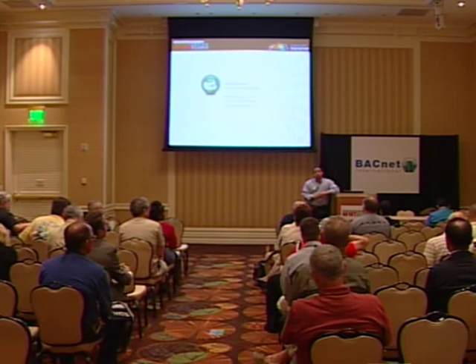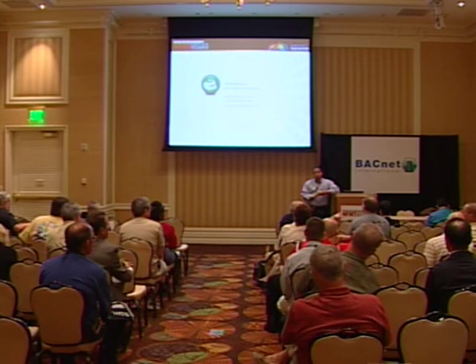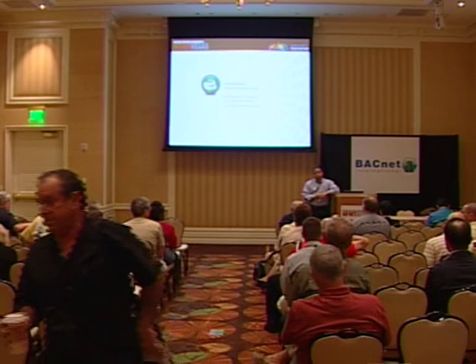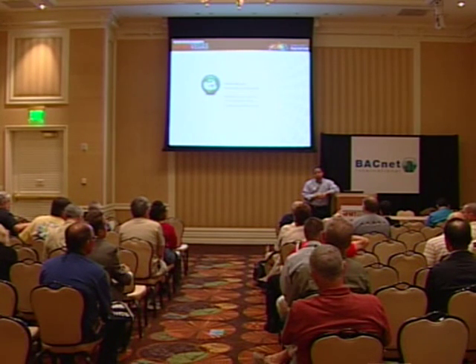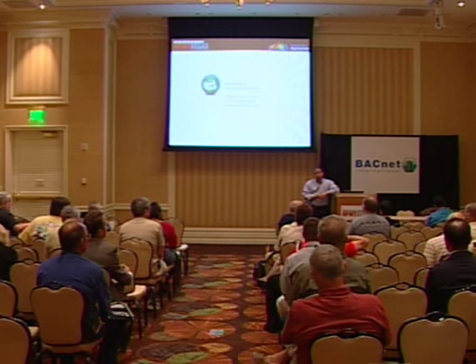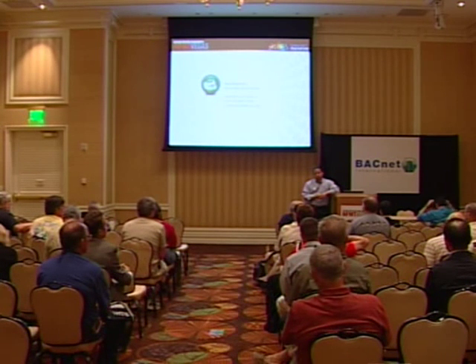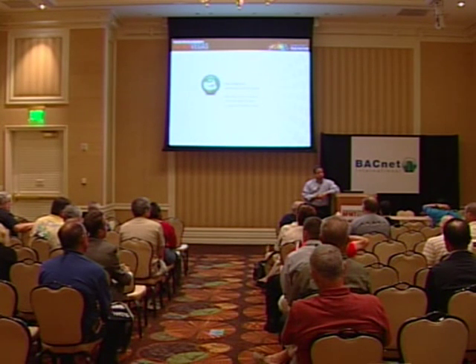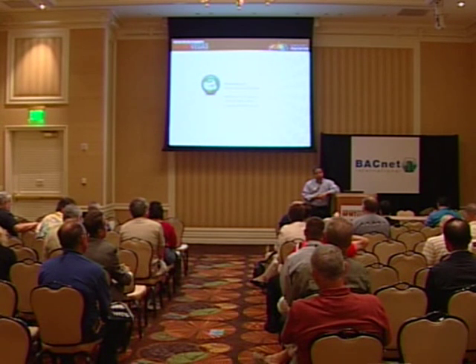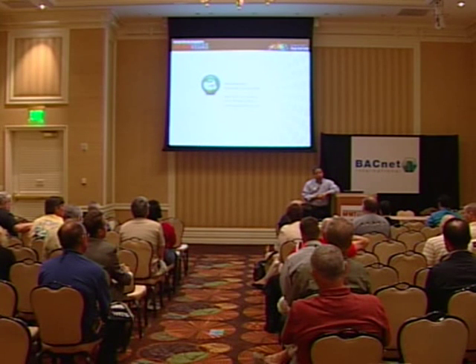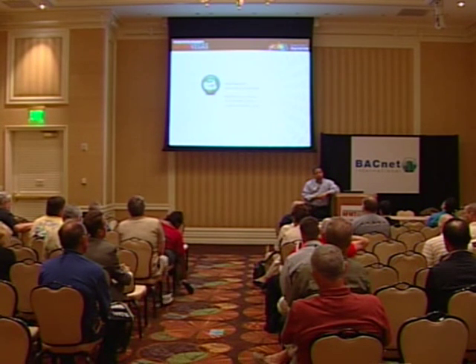Let me add a couple more things about DALI. At this point, DALI is pretty much the only protocol at the ballast level where you can co-locate the network wire with the high voltage wire to the ballast. One of the advantages of DALI is that you can get kW data for each fixture now, so you know exactly the very fine, granular data on the fixture. It will help in the long term with demand control. It also gives you information on faults related to the fixture. We get faults on all sorts of equipment, and DALI will give you that information.